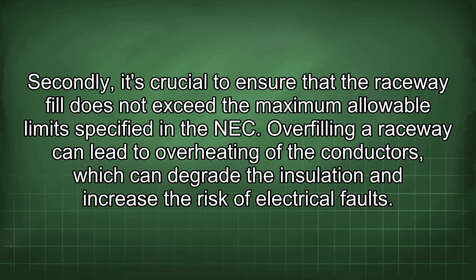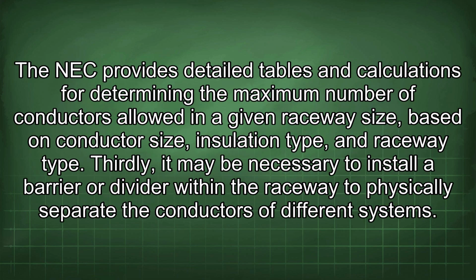Secondly, it's crucial to ensure that the raceway fill does not exceed the maximum allowable limits specified in the NEC. Overfilling a raceway can lead to overheating of the conductors, which can degrade the insulation and increase the risk of electrical faults. The NEC provides detailed tables and calculations for determining the maximum number of conductors allowed in a given raceway size based on conductor size, insulation type, and raceway type.